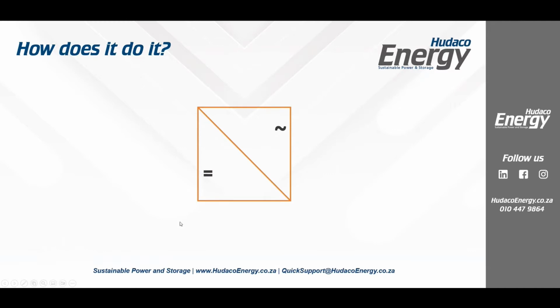Well, there's our inverter. Everybody's aware that's the symbol for the AC side. This is the DC side. We have 4 real connection points, excluding the monitoring. So let's talk about that. The first point is coming from grid, right? We call this the grid port. This is where we would connect to the distribution board. We would have a feed coming from the DB and going into the inverter.